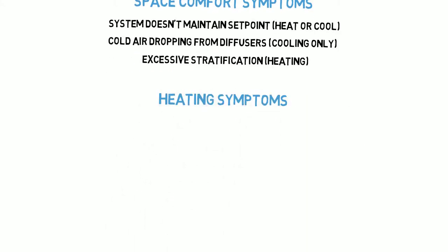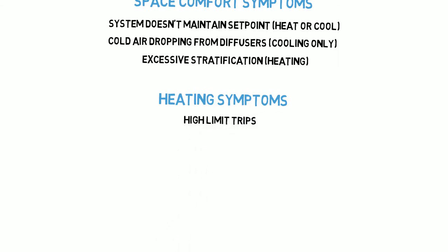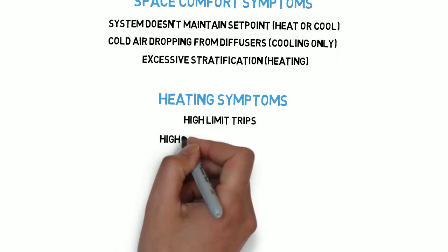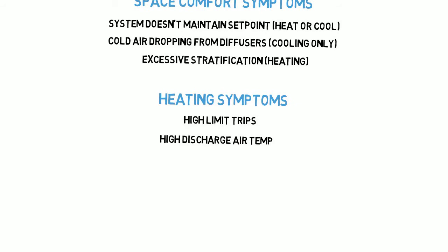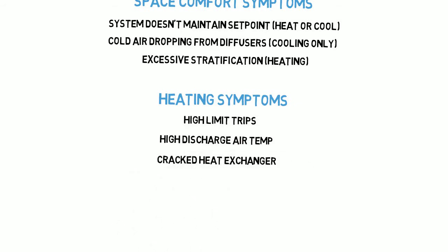Heating side symptoms of low air flow: high limit trips, high discharge air temperature, and cracked heat exchangers.